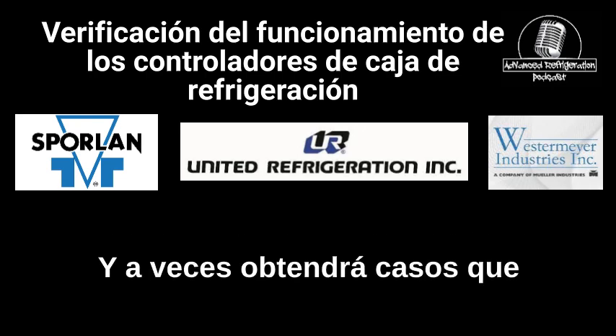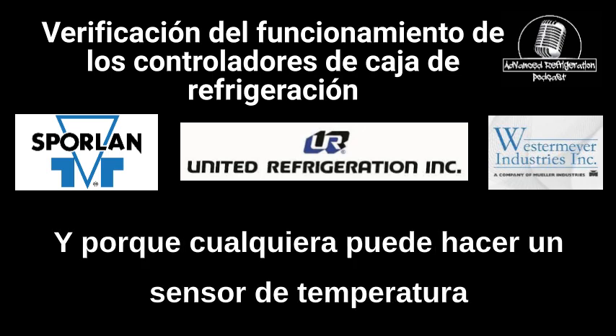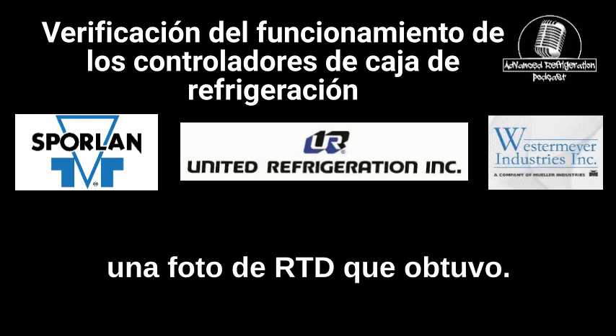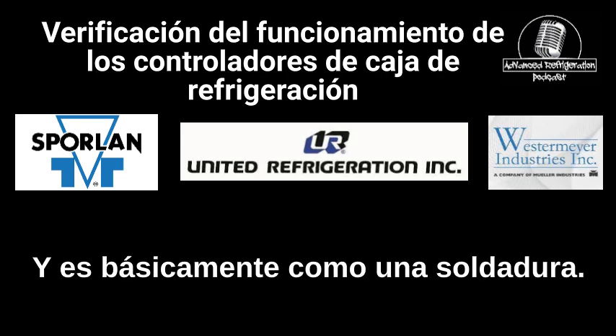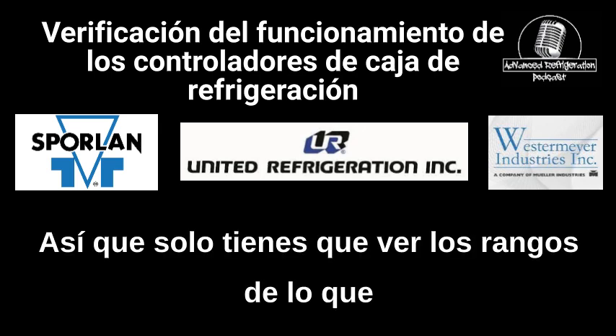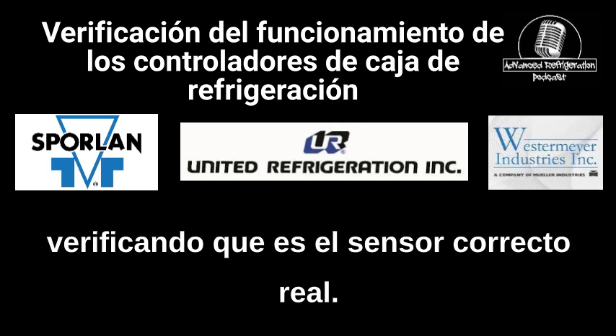Sometimes you'll get cases that have aftermarket style temperature sensors, and because anyone can make a temperature sensor, I saw Squires the one day, he sent me a picture of an RTD that he got. He's like, yeah, these are the same thing as Microthermal, and it's basically a solder-on, you could solder the thing onto the wires. So you just have to watch the ranges of what you're putting in there and what's actually in there, and verify that it is the correct sensor.